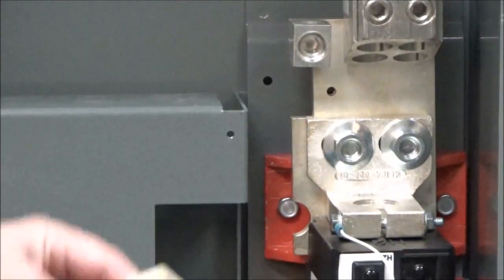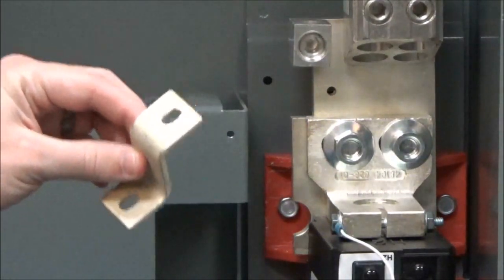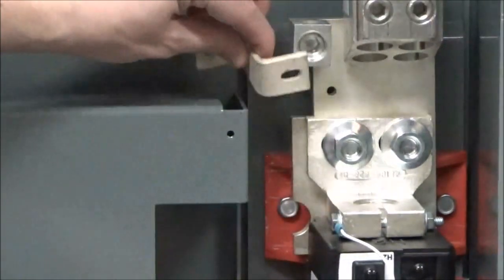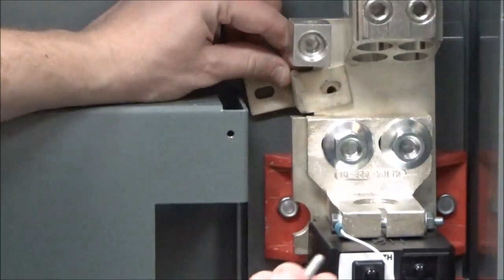If you're using it as service entrance equipment, you also need to attach the neutral bonding strap to these holes using the two screws provided.